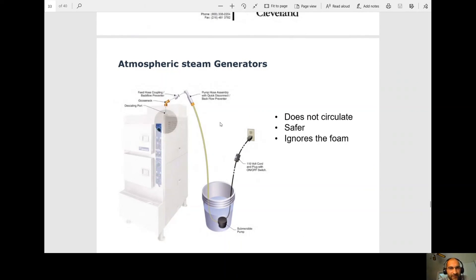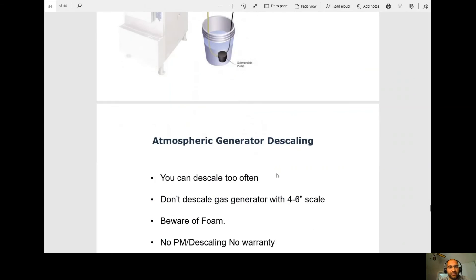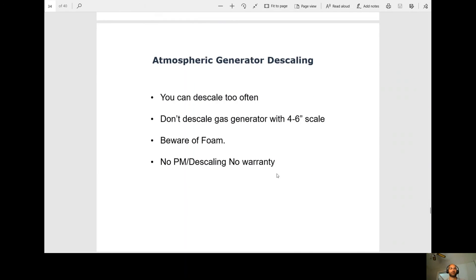So this is how we would descale the atmospheric steam generator. So they're using the pump here, but we could easily just go through this descaling port at the top and pouring our solution from there. So with the atmospheric, same as the pressure boilers, you can descale them too often. Any gas generator that has 4 to 6 inches of scale, do not descale them. They are most likely going to leak if you remove that. Be aware of foam, meaning if it foams up. So we get foam when foam hits scale and there's no water there. It doesn't mean it's full. It means that it's hit scale. You need to add the total recommended amount. And same thing, if they're not doing PMs or descaling, the warranty will be voided.